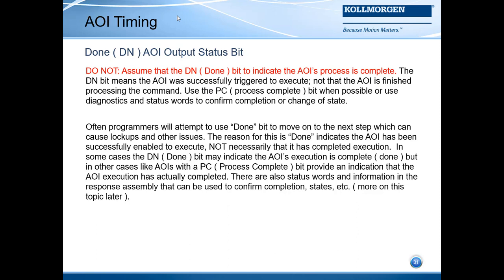Use the process complete PC bit when possible, or use diagnostics and status words to confirm completion or change of state. Often programs will use the done bit to move on to the next step, which can cause lockups or other issues. The reason for this, again, is the done indicates the add-on instruction has been successfully enabled to execute, not necessarily that it is completed execution.